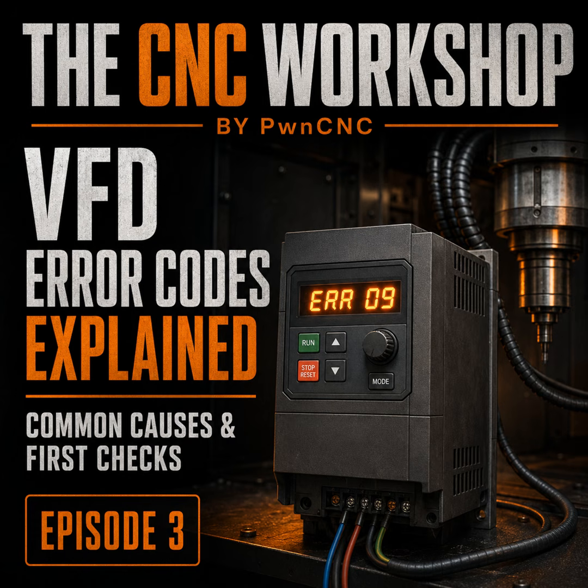I'm cutting a deep full-width slot with a large bit. The VFD shows ERR09. I stop the machine, photograph the code, record my cutting parameters, and perform a controlled test with a shallower cut. Good. If the lighter operation works normally, that is strong evidence that the original cut exceeded the available torque.